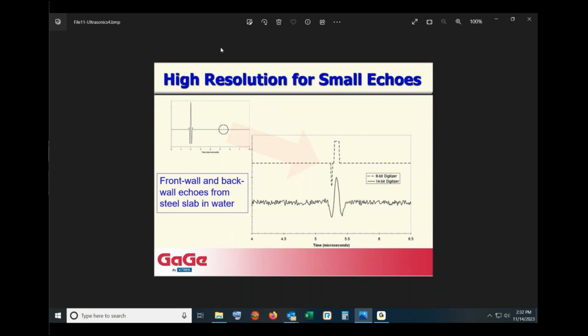And then if we go to flaw echoes that can occur between these two echoes, those again can be arbitrarily small. So for steel and water, the very best case for an 8-bit digitizer is 2 levels, which stinks, I'm arguing. If we now look at a 14-bit digitizer, where we have, again, 2 to the 6, 64 times more levels, we can really get a good view of this echo. So that, again, illustrates the power of high resolution in ultrasonics.